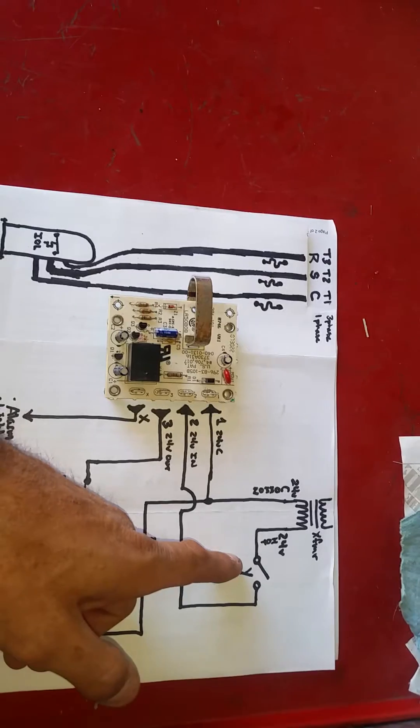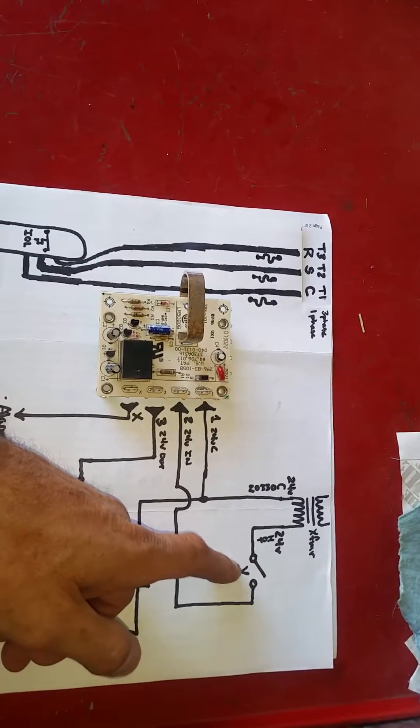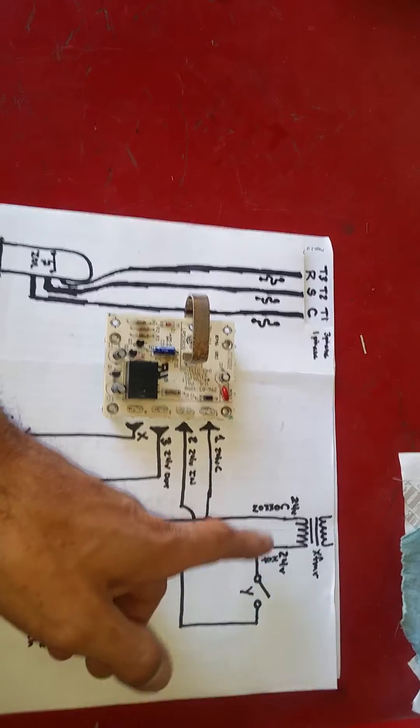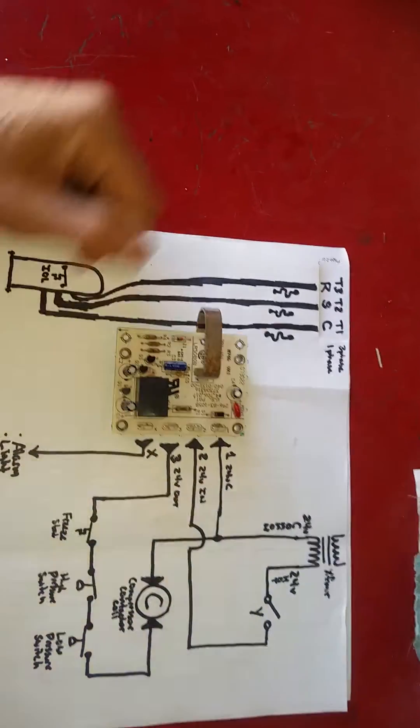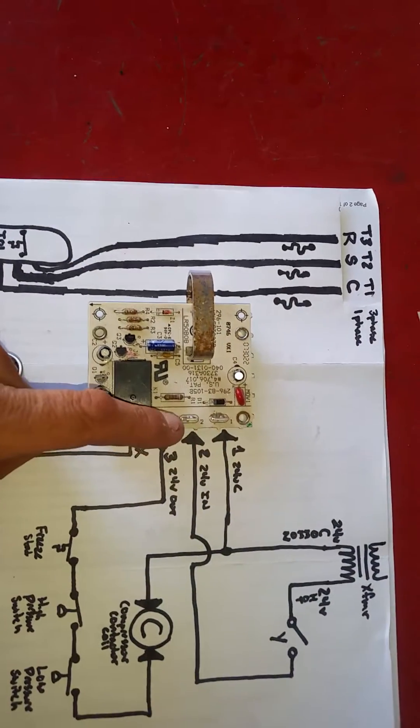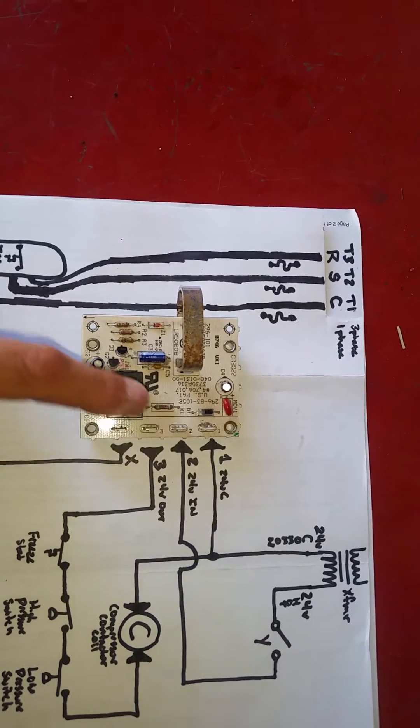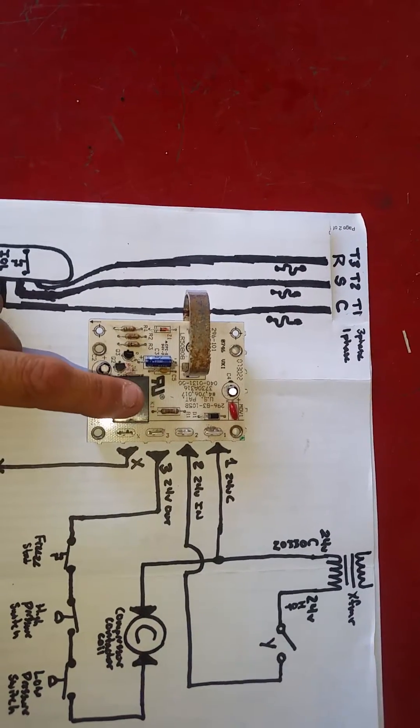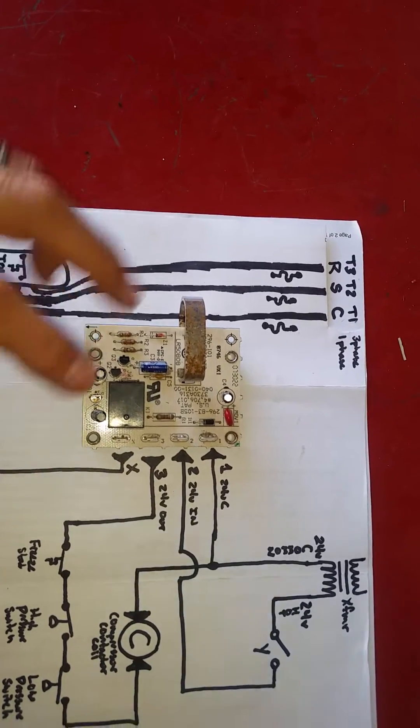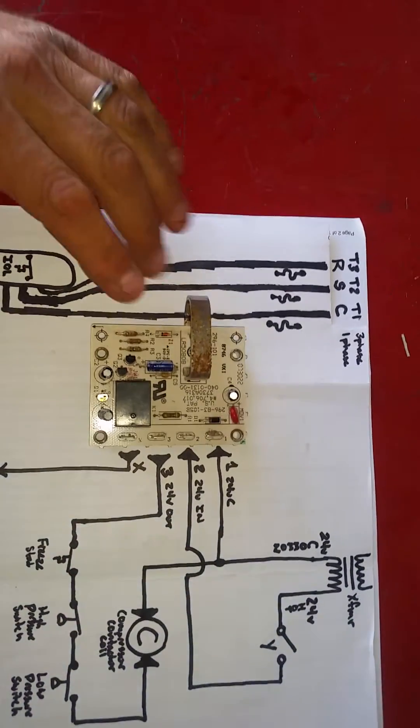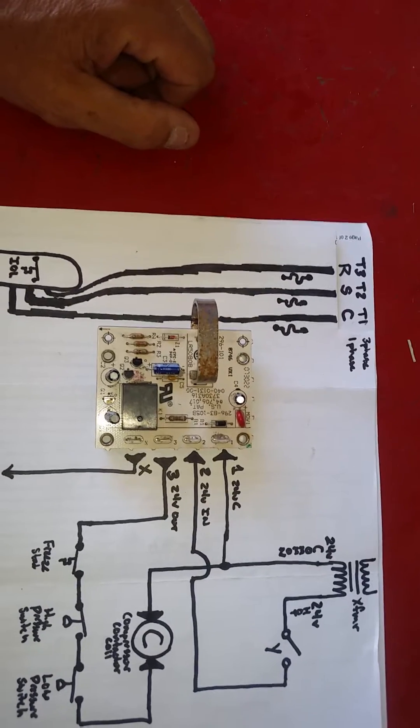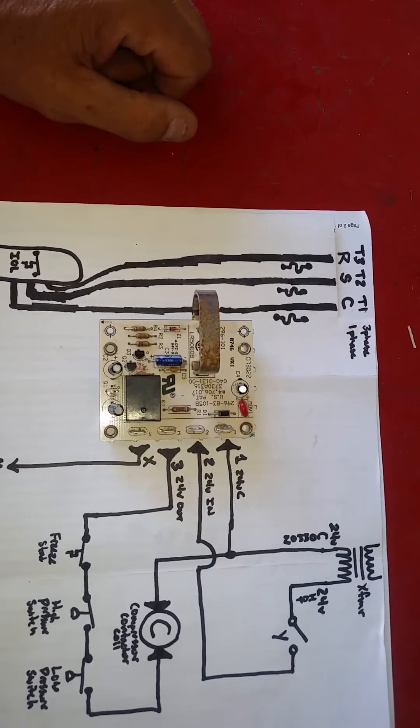When there's a call for cooling, our thermostat closes the Y, and sends 24 volts from our transformer to our CLO board, to pin two. We need to realize that this is a normally closed relay. This board is considered de-energized, or not in function at this moment. It is in a de-energized state.